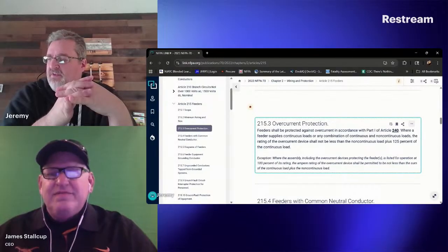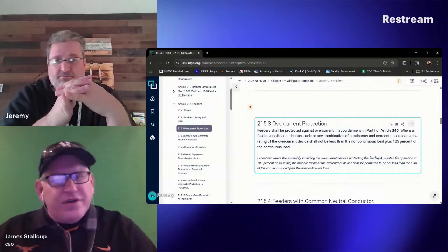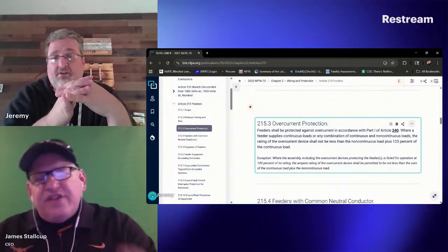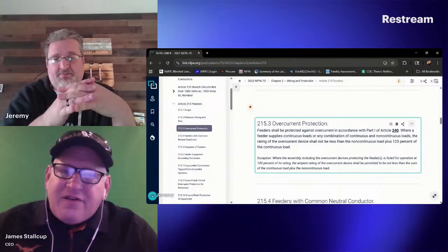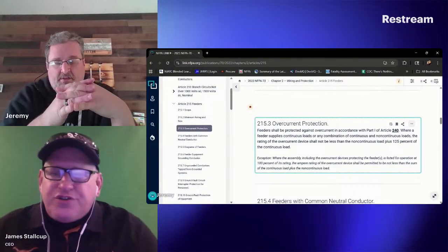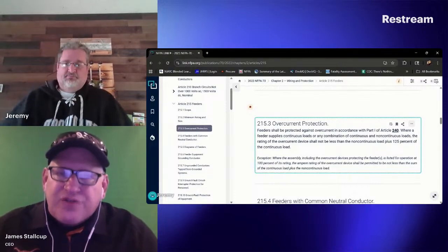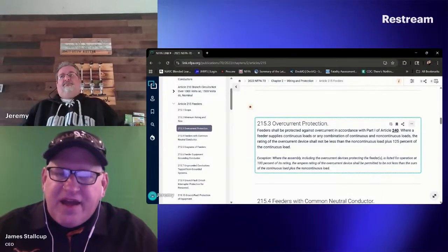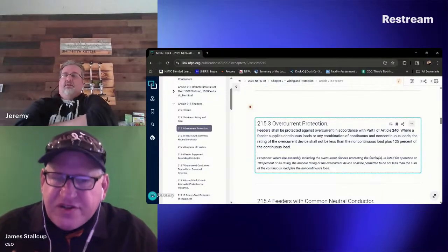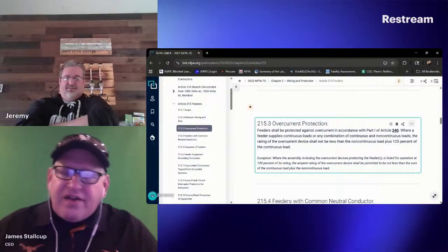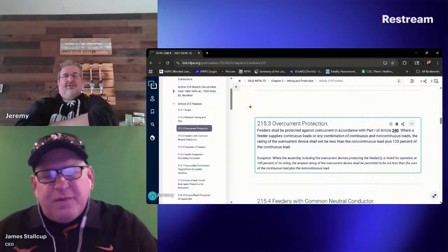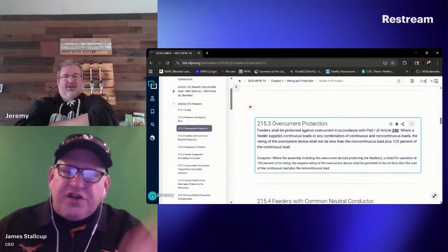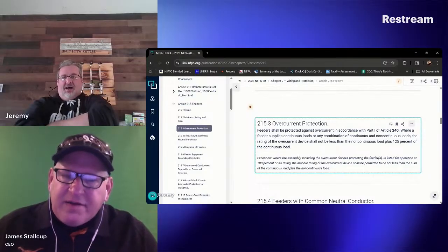So then you're violating the second sentence in 215.3. No, you're not violating it. And yes, the reason, you are, because it literally says that. Let me explain. You know why you're not violating it? Because they realize that once you're over 800 amps, all those loads are not going to be operating at the same time, and there's a diversity in there. Therefore, they allow you to go down knowing that your breaker is going to be large enough. They just want to make sure that the conductors are large enough for the load that you calculated.